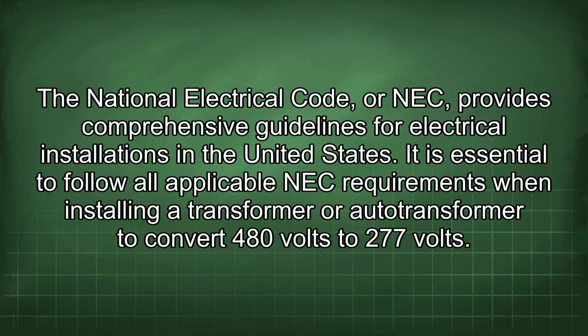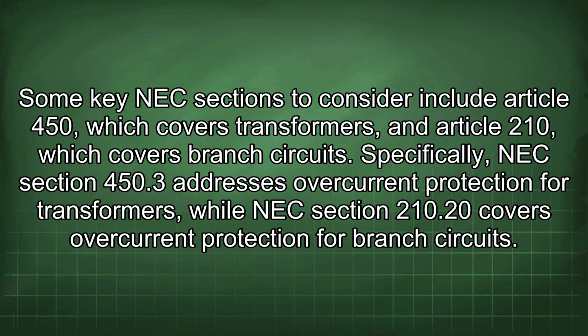The National Electrical Code, or NEC, provides comprehensive guidelines for electrical installations in the United States. It is essential to follow all applicable NEC requirements when installing a transformer or autotransformer to convert 480 volts to 277 volts. Some key NEC sections to consider include Article 450, which covers transformers, and Article 210, which covers branch circuits. Specifically, NEC Section 450.3 addresses overcurrent protection for transformers, while NEC Section 210.20 covers overcurrent protection for branch circuits.